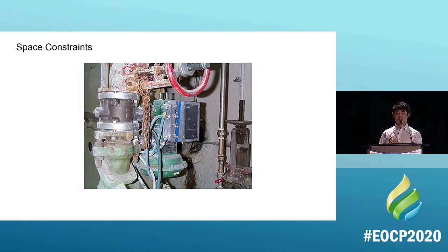Oftentimes we all have these good ideas, and then when the poor installation guy or operator goes to work on it, he's like, hey, I can't even access this valve. I can't even see this actuator because it's so cramped. And in this case, we had real issues with how to fit this actuator, and we had to orient it in this exact orientation in order to get that actuator in.